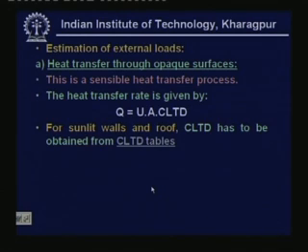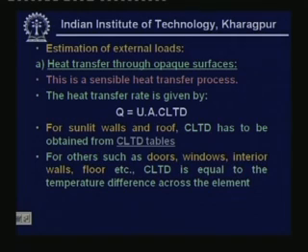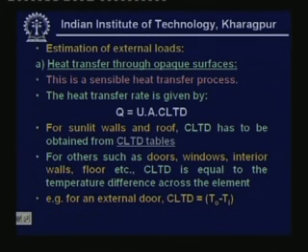CLTD tables are used for all sunlit walls and roof. For other elements that are not sunlit or have very small thermal capacity — such as doors, windows, internal walls, and floor — the CLTD is simply equal to the temperature difference across the element. For these elements the heat transfer rate is simply Q = UA × (T_out − T_i), where T_out is the design outdoor temperature and T_i is the design indoor temperature.